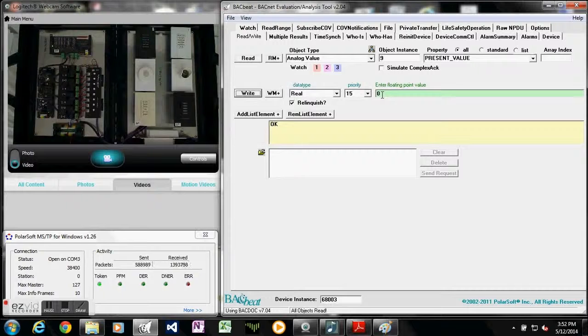So there's a table in the back of the Nexus system manual that lists all the various values for the different colors and different flash patterns that you can assign to the different LEDs. And like I said, you can choose anywhere between 7 different colors or flash patterns for the LEDs. And to turn them off, just again is a value of 0. Just write the 0 to your AV. And then AVs for the sensors are just empty objects because there's no pilot lights for the indoor sensor or the outdoor sensor.